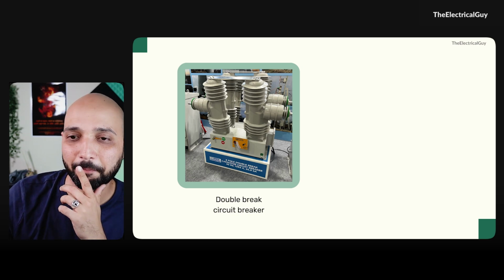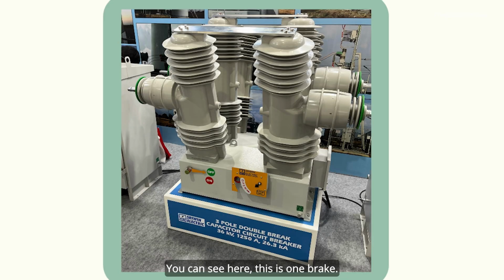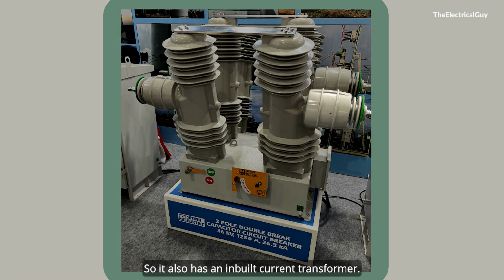This is the breaker used for that particular application, a double break design. You can see here, this is one break, this is the second break, connected in series with each other. This is where I'll connect the incoming line, and this is my outgoing line. The outer portion you see is a current transformer, so it also has an inbuilt current transformer.